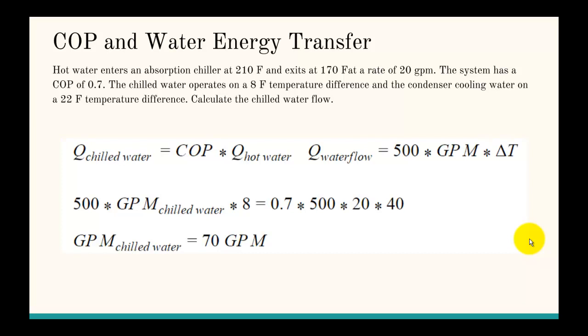One of the big points with this is that the condenser cooling water temperature difference isn't going to have an effect on our problem because the energy input in this absorption chiller is the difference in the hot water, is the hot water heat flow. That's going to equal, when we take into account the efficiency, the COP, the output, which is the heat that we put into the chilled water, or the cooling that we put into the chilled water in this case.